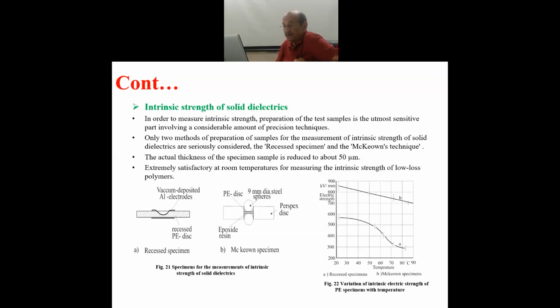850 kV per millimeter. And another thing, the breakdown strength has been measured with increasing temperature. When the temperature increases, it affects adversely the strength of the solid dielectric. And as you can see, the lower breakdown strength is measured at higher temperatures, to the tune of, say, 80 degrees centigrade. When it is normal temperature, of the order of 20-25 ambient, the breakdown strength is of the order of 850 kV per millimeter. It's a very, very high, unbelievable breakdown strength. So that cannot be measured in a simple fashion everywhere.